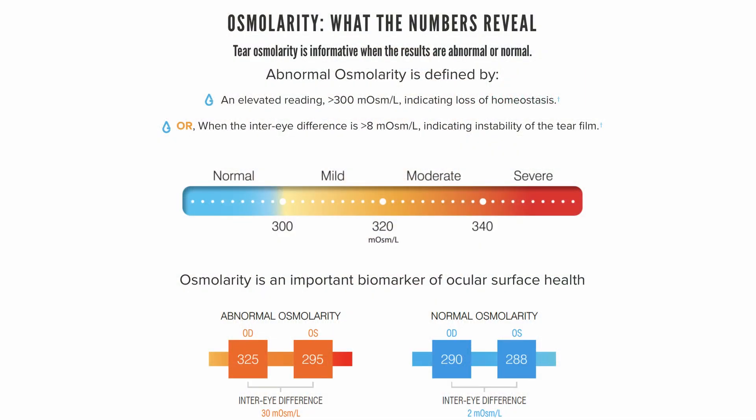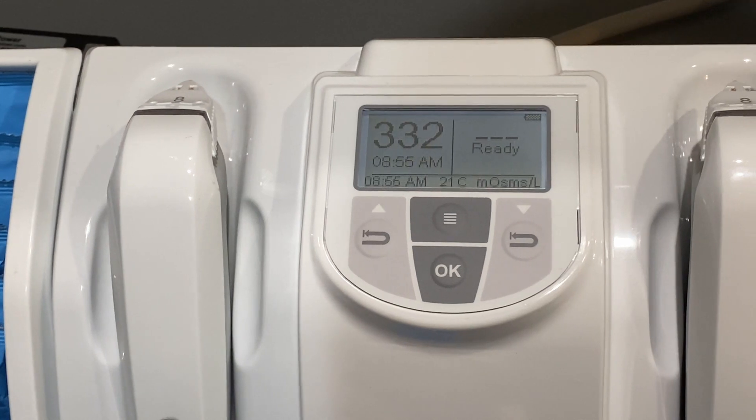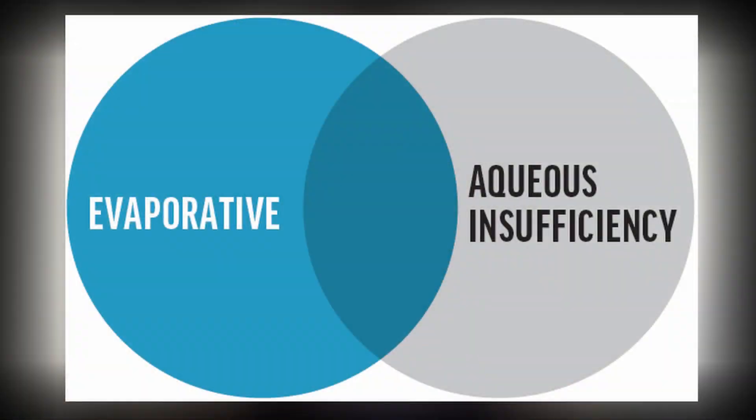The TearLab is a very precise test, shown to be even more precise than universally accepted point-of-care tests such as cholesterol and glucose in diabetes. The higher the numeric measurement, the drier the eye — it is measured in milliosmoles per liter. The TearLab defines an abnormal osmolarity as an elevated reading greater than 300 milliosmoles, or when the difference between the two eyes is greater than 8 milliosmoles per liter, indicating instability of the tear film. The results indicate whether a patient has dry eye, including severity. However, it cannot tell you the reason why — we are unable to tell if the patient has aqueous-deficient dry eye or evaporative dry eye. Additional clinical tests and questionnaires are all important to further classify the type of dry eye, or in the case of a normal osmolarity in a patient with symptoms, to determine if it could be mimicking dry eye disease.